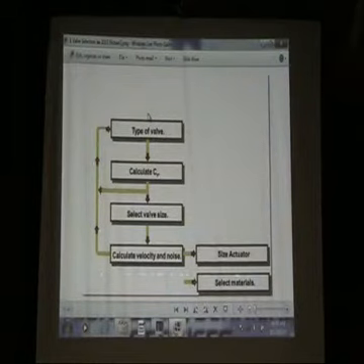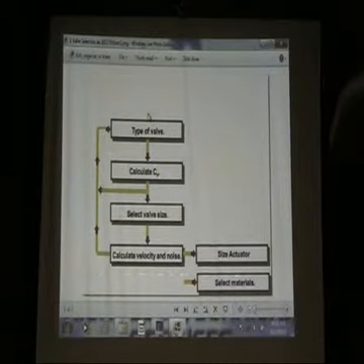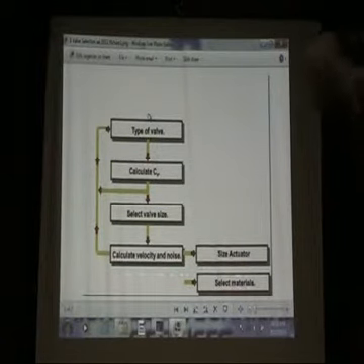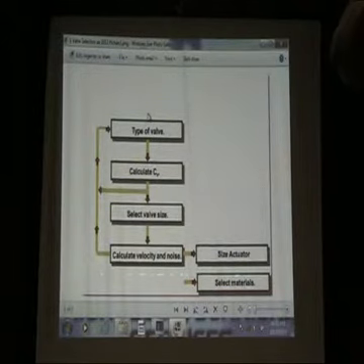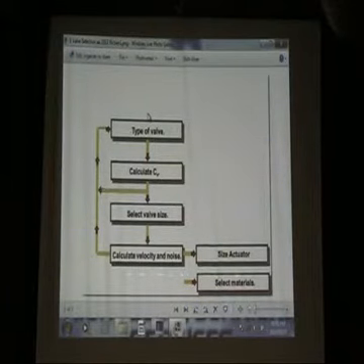You can't put it in like this because the disc is wider than the body. When you close this thing, you install it in the line, okay? Then they put the bolting and stuff. The problem is then they tighten it. So you need to close it first. Now they install it in the line. They put the bolts through, there's the flange. By the way, this is what they call a wafer type. It's got no flanges. A flange is a round piece of metal with a lot of holes. In your pipeline, the pipe will come here, it's got a flange, and the other side the same.